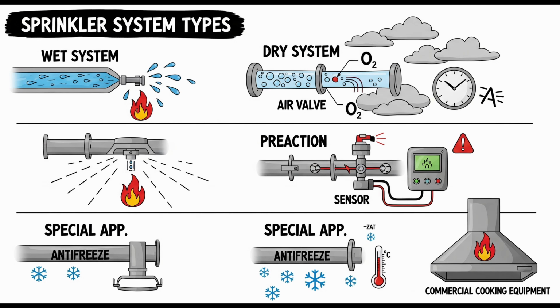Okay. Finally, briefly on deluge systems, we touched on them. Right. Deluge systems are simpler in concept in that they use open sprinklers, no heat-sensitive elements on the heads at all. Just open nozzles. Yes. When the fire detection system activates, the deluge valve opens, and water flows through all the sprinklers or nozzles on that system simultaneously. It literally deluges the entire protected area very quickly. Total flooding. Exactly. The source notes that their detection systems must be automatically supervised, just like pre-action, and the systems must be hydraulically calculated to ensure adequate flow and pressure can be delivered from every single open head at the same time. Makes sense. If everything opens, you need massive flow, used for high-hazard areas needing immediate widespread application. Precisely. Think aircraft hangars, chemical storage, anywhere you need to knock down a potentially fast-spreading fire over a large area instantly.